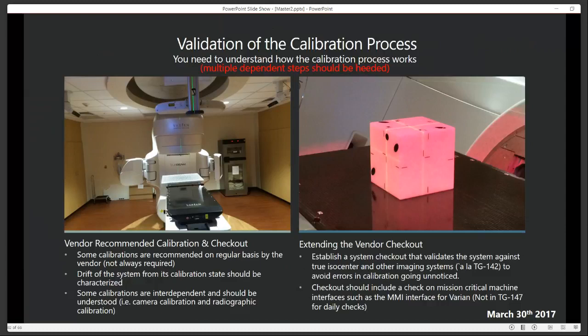And so all of that needs to be understood, and it does need to be extended, because when you do the daily checkout, you're basically looking at the relative position of the cameras, not necessarily the true accuracy of the system. So I don't mind to know that camera 1 is not moved relative to camera 2, camera 2 is not moved relative to camera 3, but that doesn't tell me about the accuracy of the system at IsoCenter.